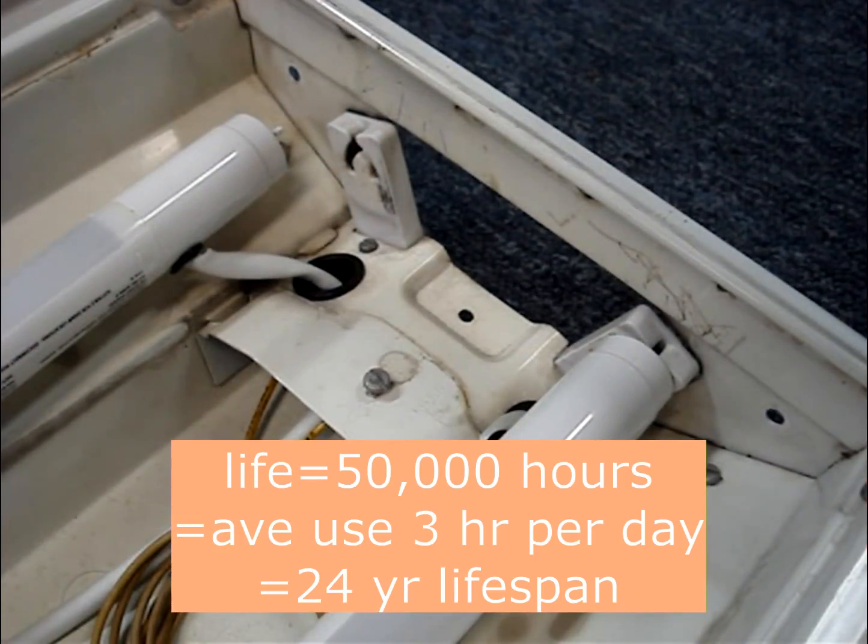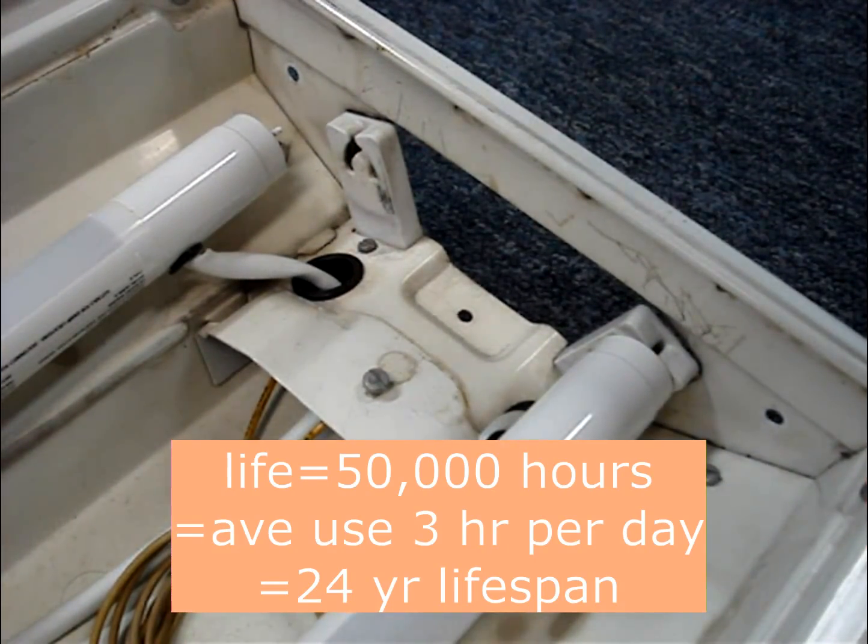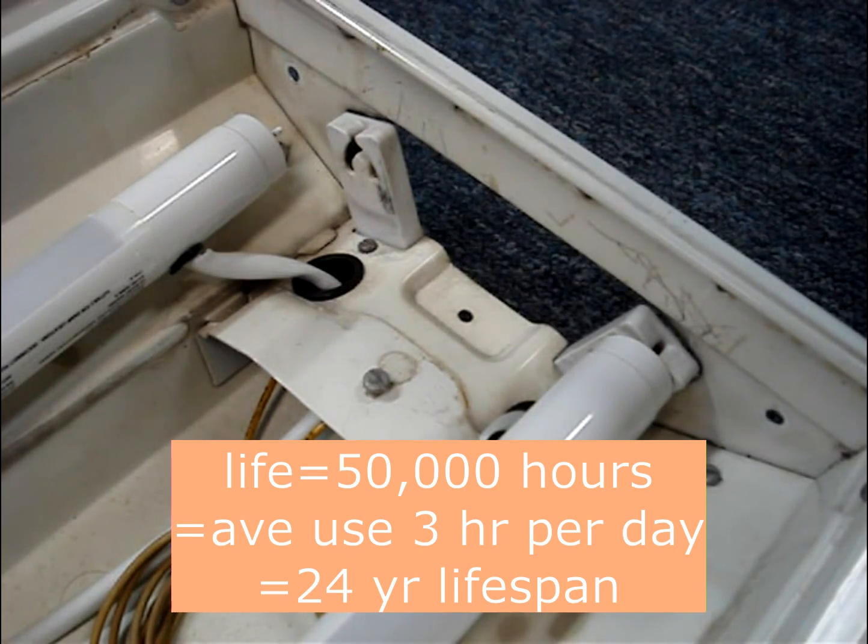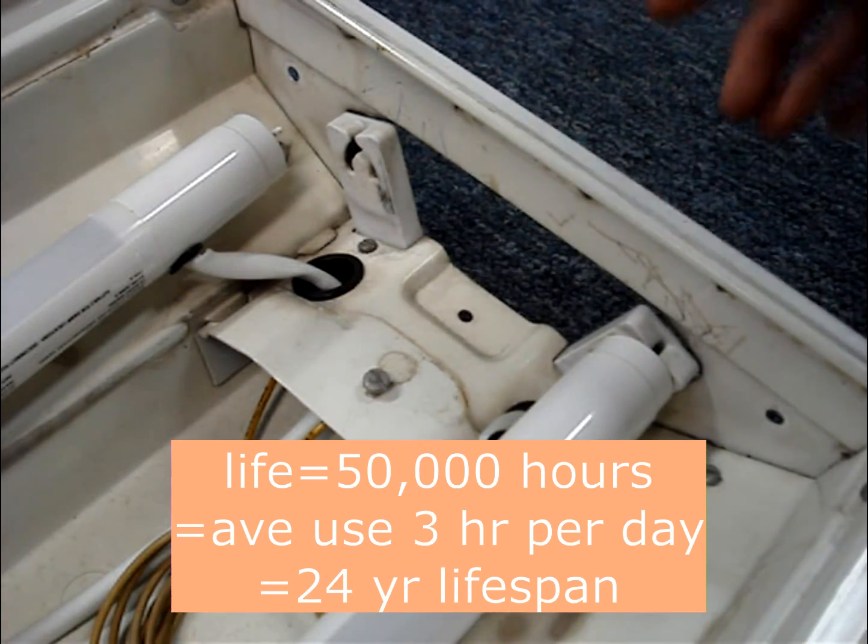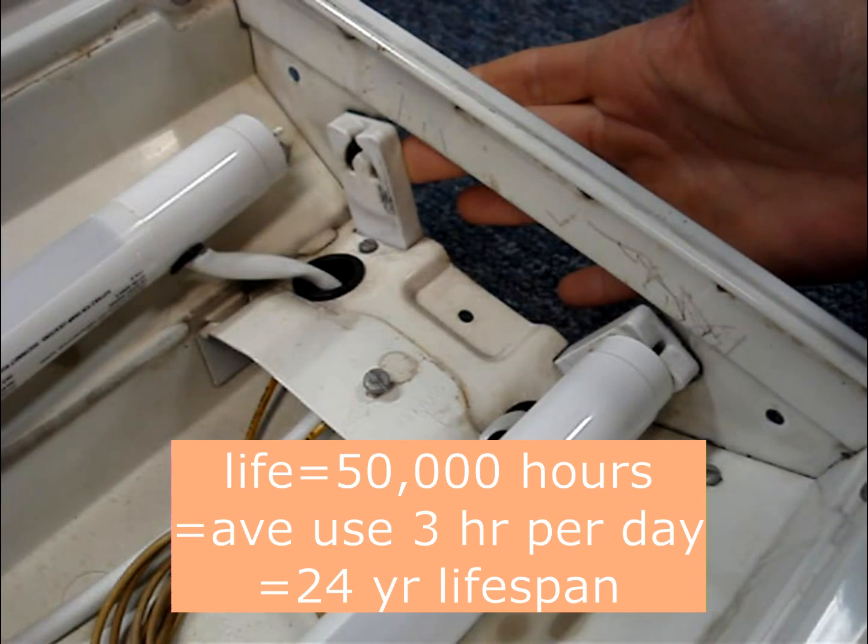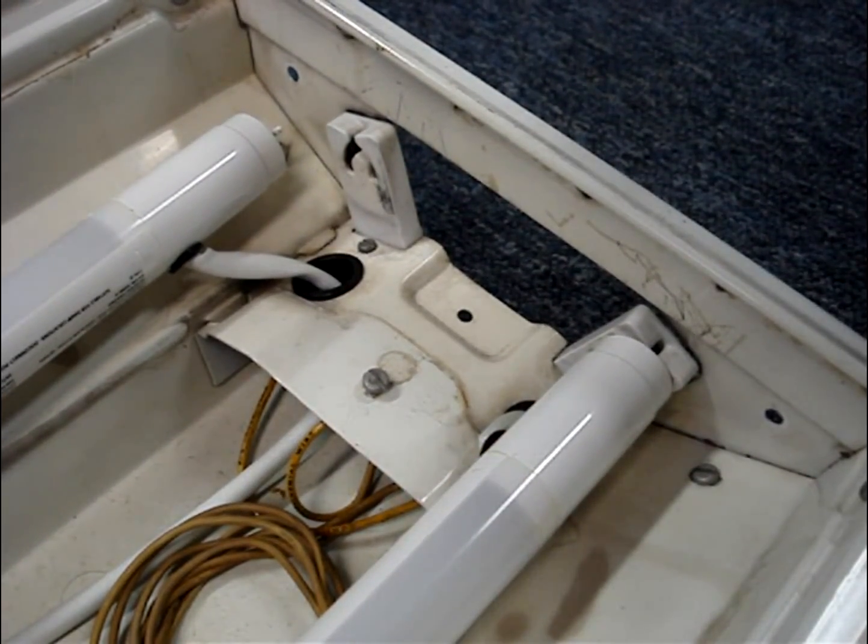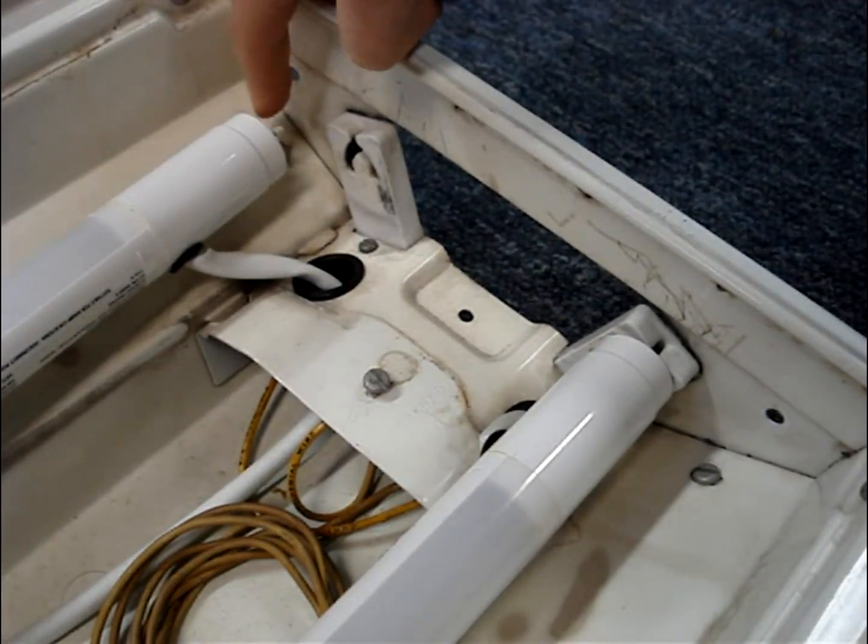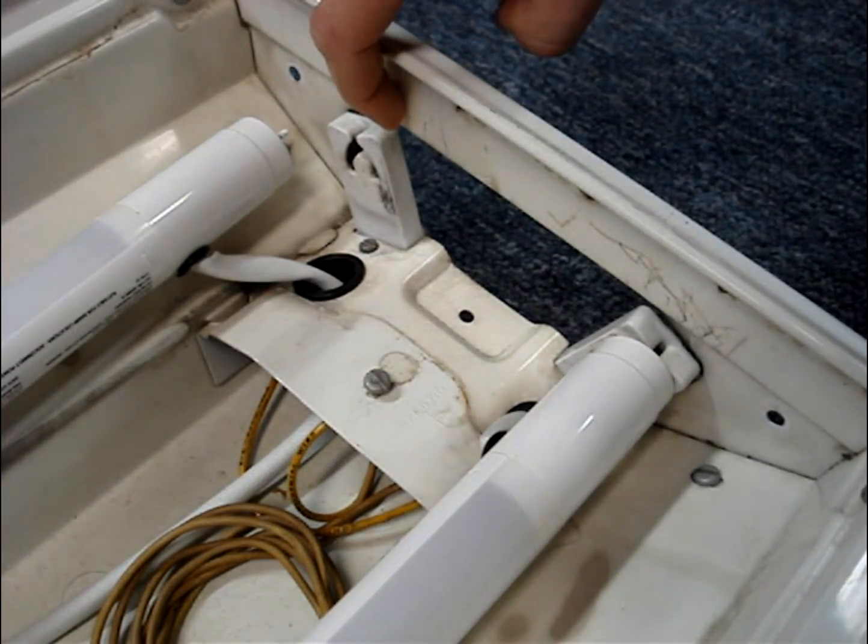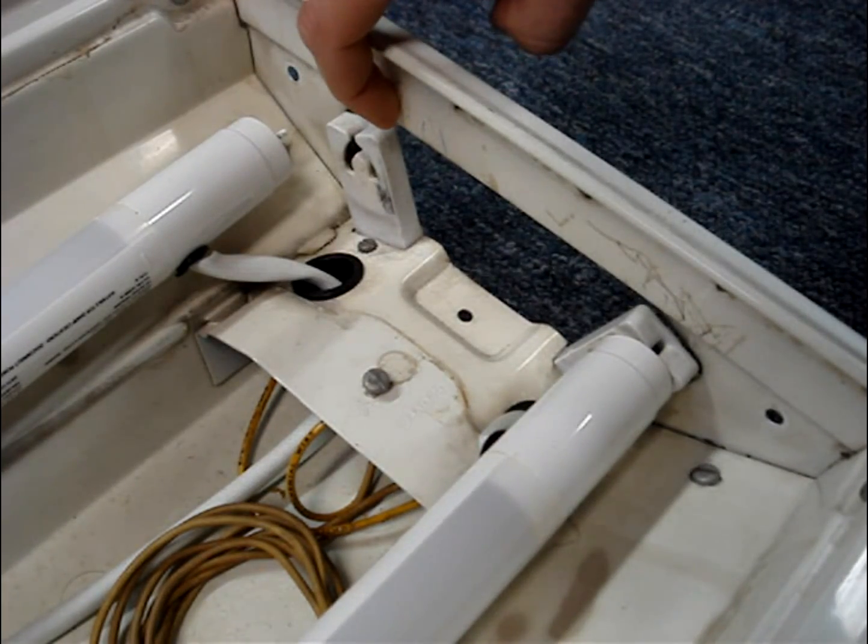Another good thing about these is that if down the road somebody doesn't know what's installed in this light and they try to put a tube into the sockets that's not compatible, you won't have any bad things happen because there's no energy on these sockets. Also, if somebody tries to change the bulb hot, you can't get one of these pins against the frame of the light and have an electrical hazard.